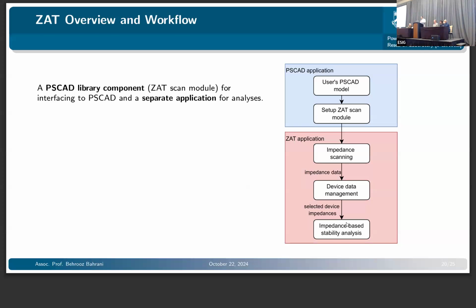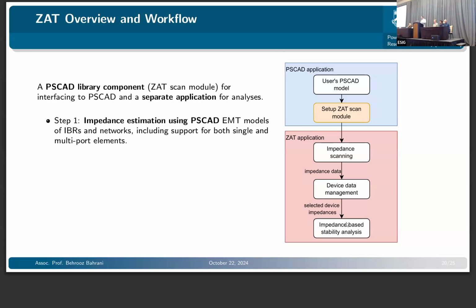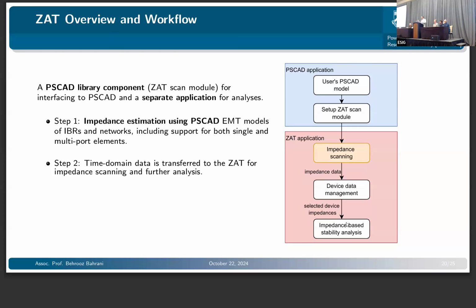A closer look at the tool. The way it works, for the moment, is mainly for the PSCAD environment. So there is a module you would put in your PSCAD, and that module then interacts with an external application, and you can do the analysis there. The first step is to set up your impedance scan module within PSCAD and give certain parameters there. And then the tool will obtain time domain data from PSCAD, bring it to the interface, and it will scan the impedance for you.